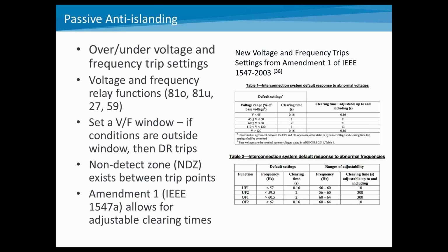adjustable. So in terms of functionality from a relay protection setting, there are things like the 81 over and under frequency, 27 and 59, or over and under voltage trip points. And if your DR is outside that particular window, then it's basically going to trip. Now, when you use a passive anti-islanding technique, there is what they call a non-detect zone if your voltage and frequency is being maintained within those areas.